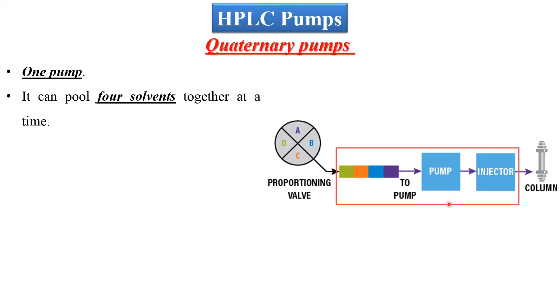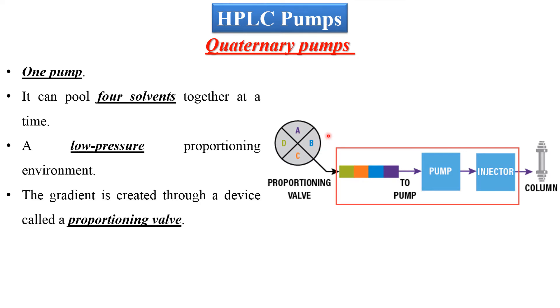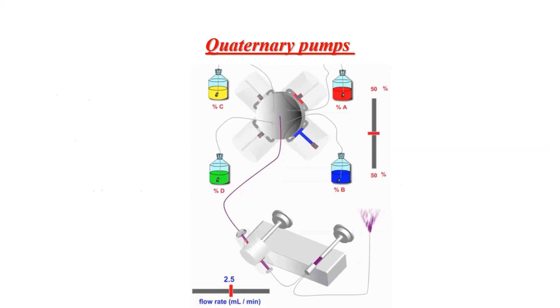The second type of HPLC pump is the quaternary pump. This is a sample design: as we can see, there is only one pump unit and it can deliver up to four solvents at a time. It can be considered a low pressure environment, and the proportionating valve will control the ratio of the solvents to be delivered into the column. The solvents are mixed in the mixing chamber before reaching the column.